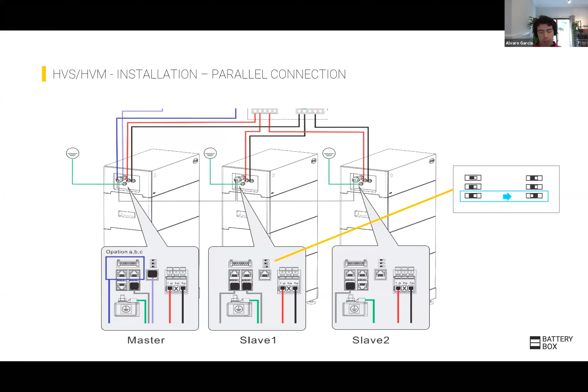And in the whole installation, the only thing that's slightly different is one of the dip switches, the one in the middle battery. So if you have 2 batteries, you don't need to do anything. If you have 3 batteries, the middle one, you will need to change the bottom dip switch. This is because it's a communication terminator. So you need to make sure that you're opening the communication terminator so it doesn't stop the communication between batteries.